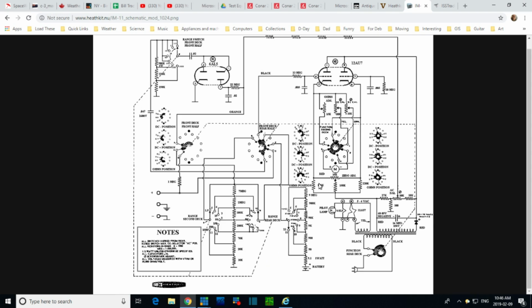So here's the string of resistors. Notice they're doing that same pattern we noticed in the capacitor checker. 999. So you add these numbers up. If you add them all up, you probably get 10 megohms. This last one is supposed to be 10, isn't it? Something similar going on? No, these are done differently. They aren't following that pattern. 99999 all the way down. Or I could say more generally XXX all the way down. Second range deck. Range rear deck.